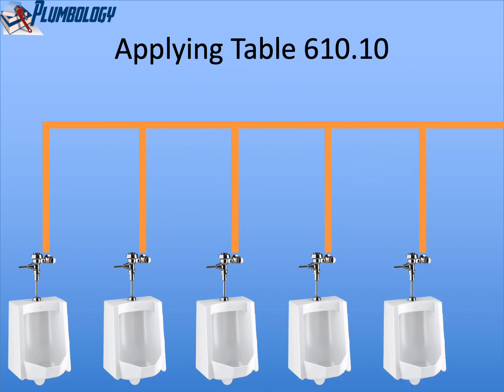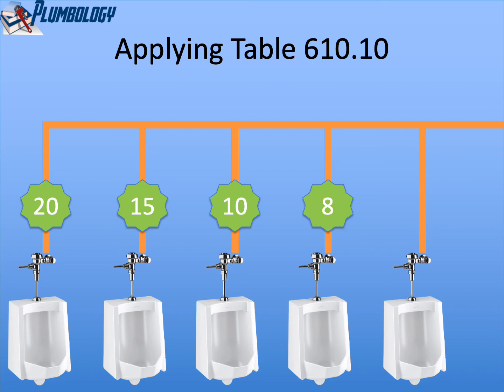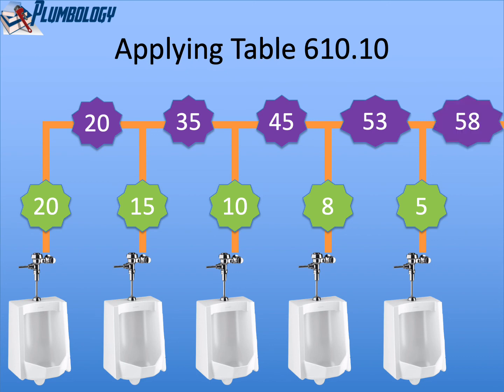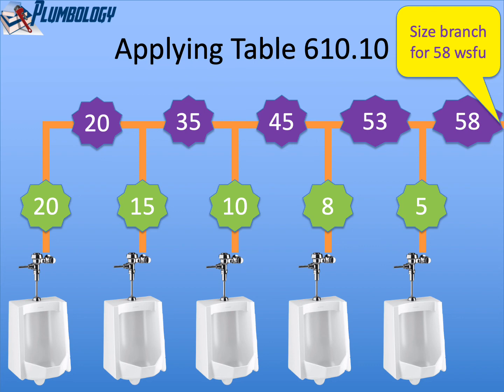And then finally, five urinal flush valves. Same decreasing scale starting with 20, next is 15, the third is 10, then 8, and finally the fifth one is 5. Going back to do the pipe segments: start with 20, add 15 equals 35, add 10 equals 45, add 8 equals 53, add 5 equals 58. That branch would be sized for 58 water supply fixture units.